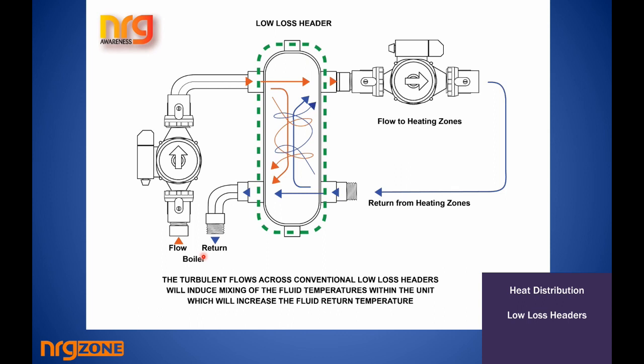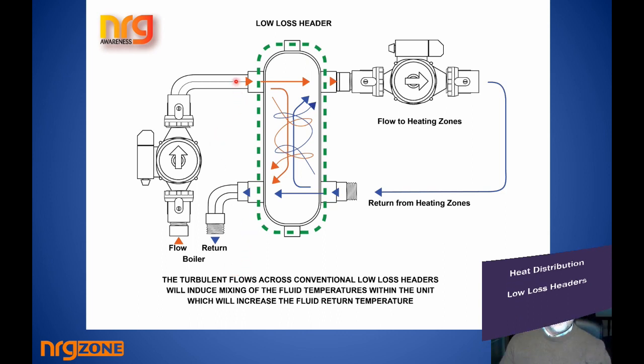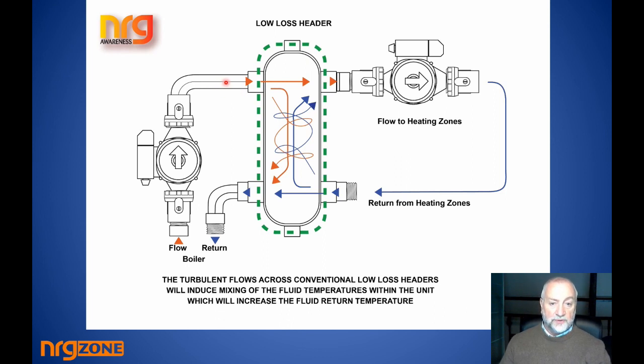It would be sulfur based if it was from oil, or it could be hydrochloric acid and the like from LPG. So it was always a good idea, with the low loss headers or with any arrangement, that you would have either a bypass from flow to return to cause the water not to be too cold, and with the low loss header that you mix some of the hot with the cold.